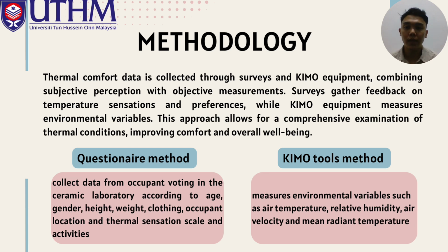For the methodology, thermal comfort data is collected through a survey and KIMO equipment, combining subjective perception with objective measurement. The survey gathers feedback on temperature sensation and preference, while KIMO equipment measures environmental variables. For the questionnaire method, we collect data from occupants voting in the ceramic lab according to age, gender, height, weight, clothing, occupant location, thermal sensation scale, and also activities. The KIMO tools method measures environmental variables such as air temperature, relative humidity, air velocity, and mean radiant temperature.